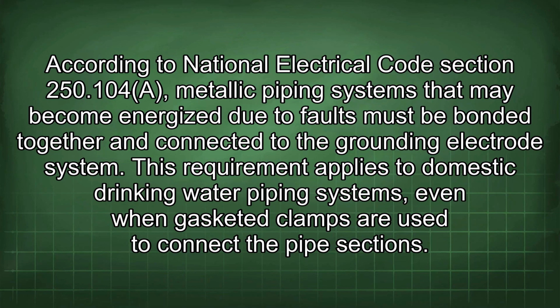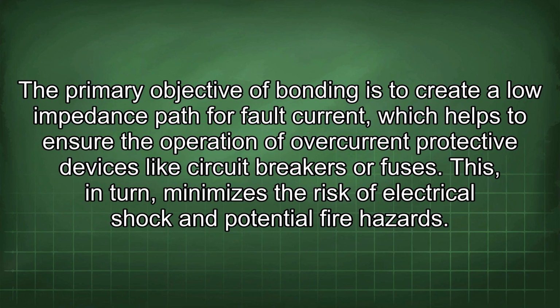According to National Electrical Code Section 250.104, metallic piping systems that may become energized due to faults must be bonded together and connected to the grounding electrode system. This requirement applies to domestic drinking water piping systems, even when gasketed clamps are used to connect the pipe sections. The primary objective of bonding is to create a low impedance path for fault current, which helps to ensure the operation of overcurrent protective devices like circuit breakers or fuses. This, in turn, minimizes the risk of electrical shock and potential fire hazards.